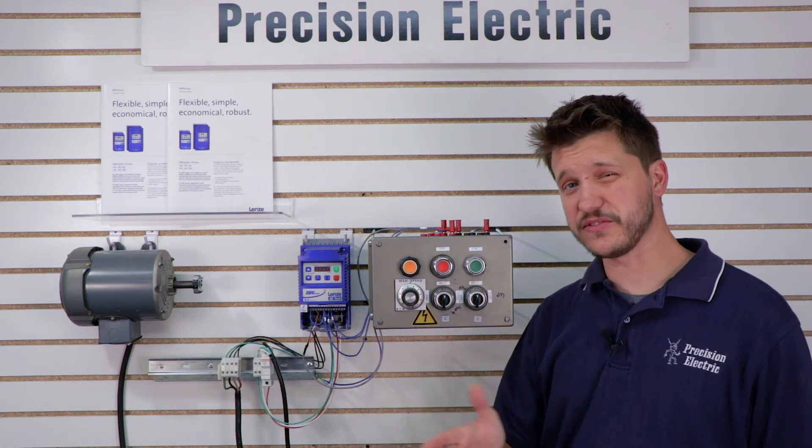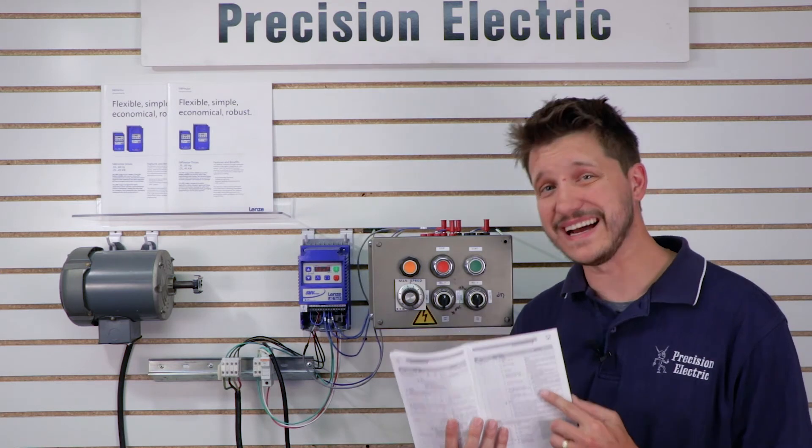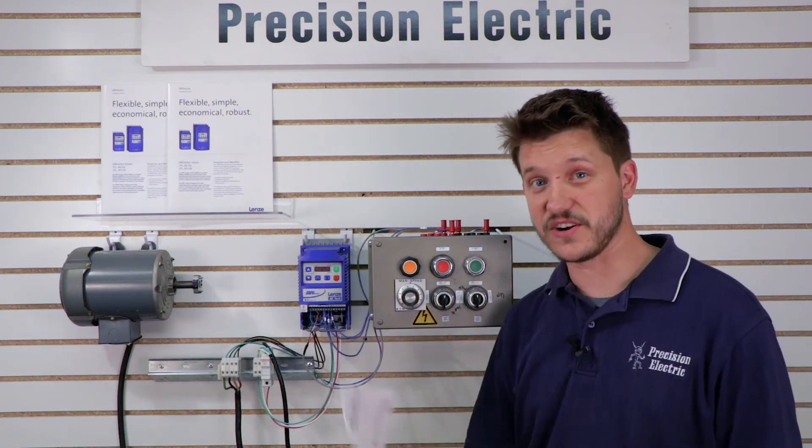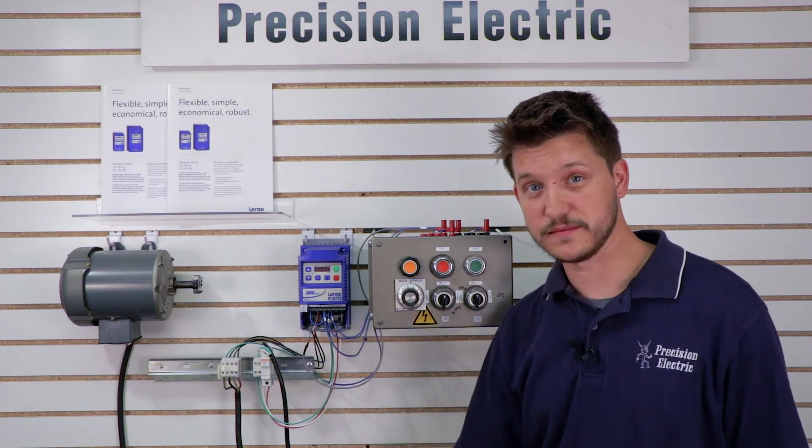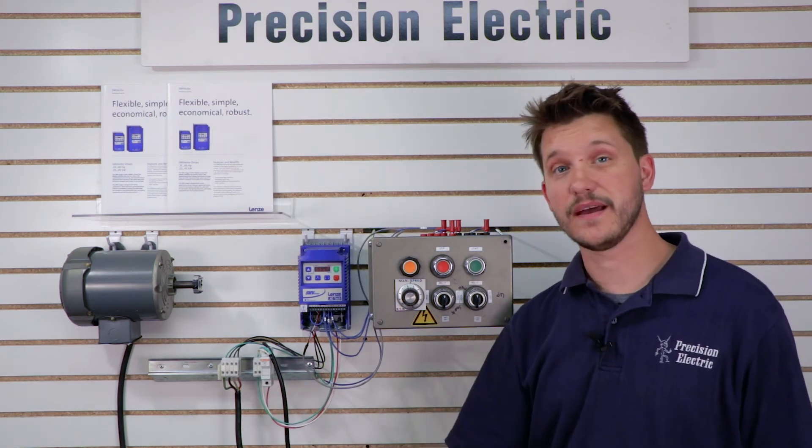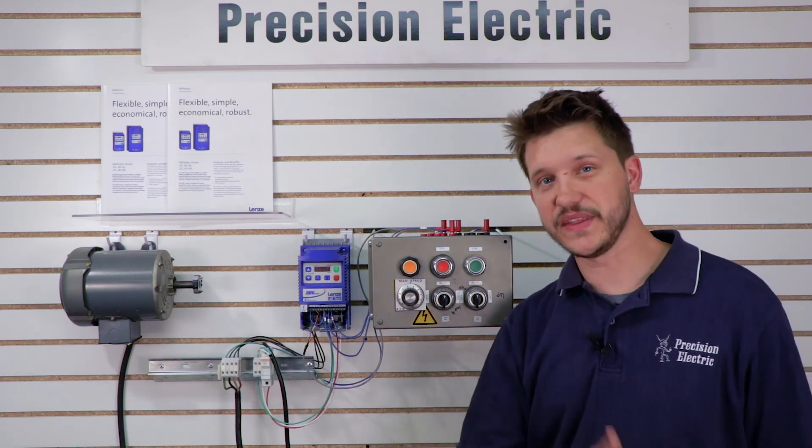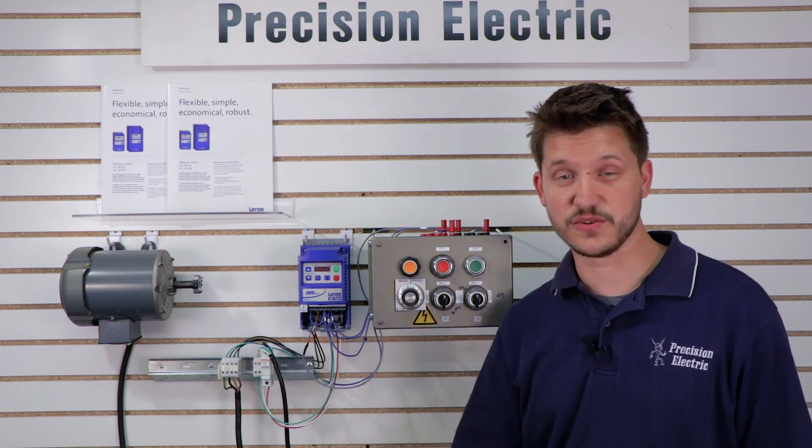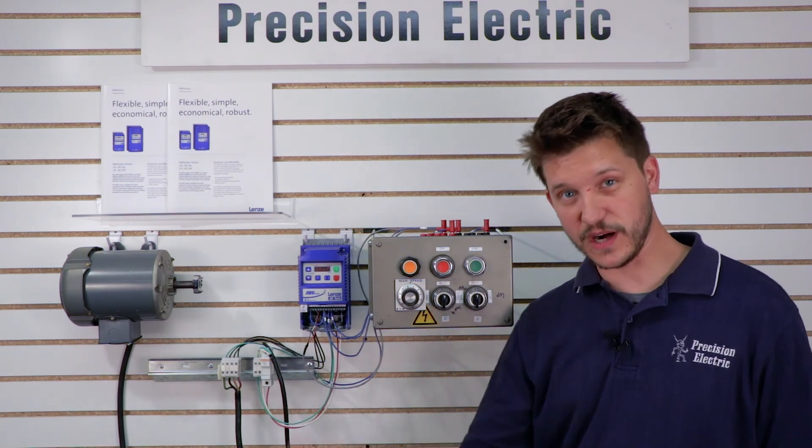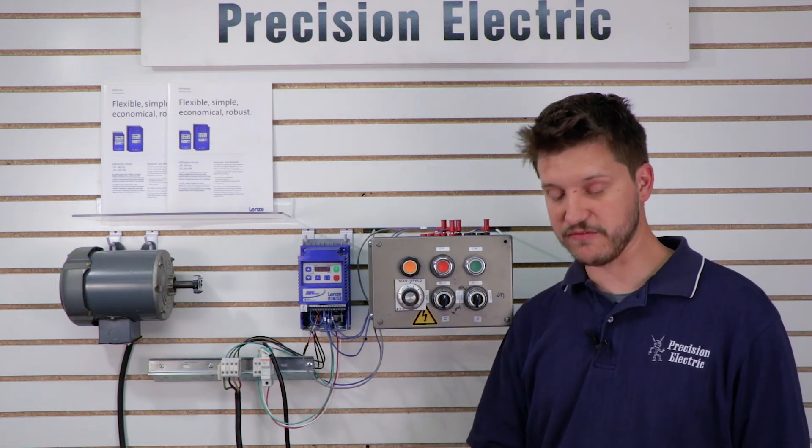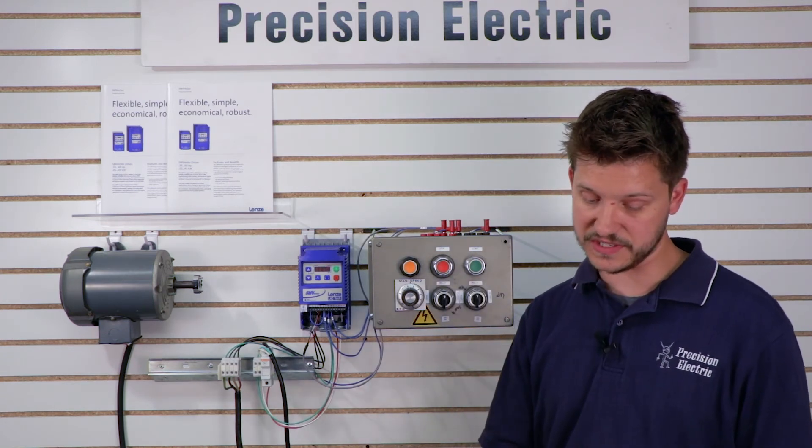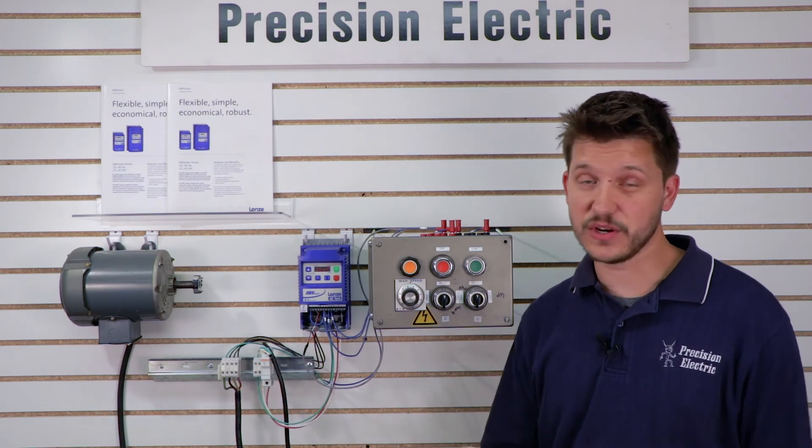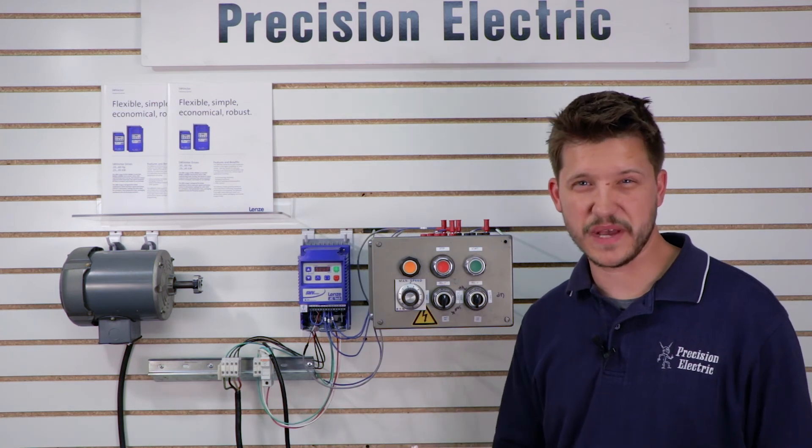The fifth option, actually all these five through eight, these are all different variations of what's called a flying restart, which is the opposite of the DC brake. The DC brake's going to inject voltage to try to stop the motor before it starts. The flying restart is going to say, hey, I'm already spinning, just try to restart while it's still spinning. So if we're in the middle of a motion, like a coast to stop, and we just like maybe the pump is still spinning because the drive faulted out, but then it came back on before the pump stopped spinning, because maybe there's a lot of inertia there, then it's going to try to auto restart it while it's spinning right where it left off. So it's not going to try to essentially slow it down or speed it up. It's going to start right where it left off and restart it back up to the speed you had it running at. And there's just different versions of flying restarts, and you want to read this little note section as to where and when you would use those appropriate restarts, because it's all application specific. And if you have any questions, I mean, you can always call us like we can help you kind of navigate through what restart kind of applies best to your application.